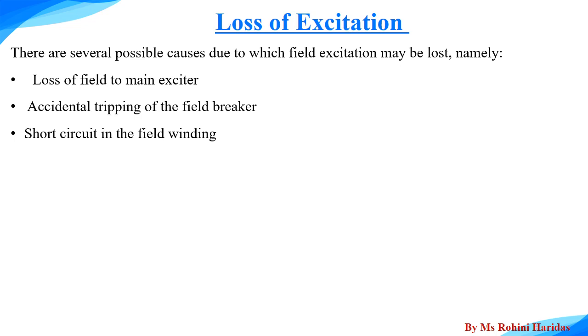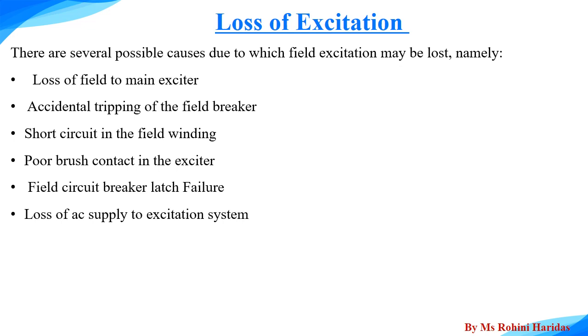The next abnormal condition is the loss of excitation. There are several possible causes due to which the field excitation may be lost. It can be loss of field to main exciter, accidental tripping of the field breaker, short circuit in the field winding, poor brush contact in the exciter, field circuit breaker latch failure, loss of AC supply to the excitation system.